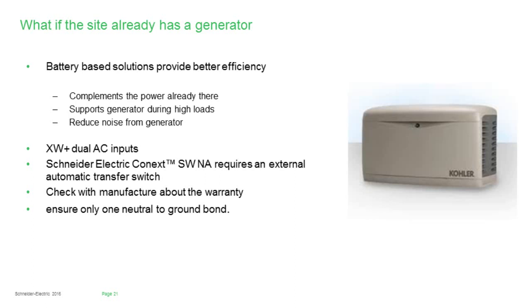And of course, probably one of the greatest benefits of choosing the XW Plus is that it has dual AC input, so you can set up charging parameters and how the system uses those two inputs distinctly. The grid source can provide maximum charging and everything else, but maybe that second input has some load support functions as well. So you don't necessarily have to size for a 20 kW generator just to make sure that everything fits. But our general recommendation is to make sure that it's at least the size of the inverter so that we can cover loads as well as do some charging.